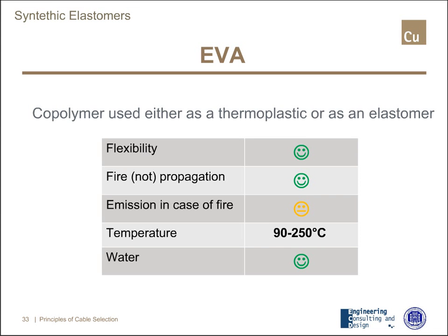EVA — ethylene vinyl acetate. Flexibility is good. Fire propagation: good. Unfortunately, emission in case of fire is not so good; again, we have to consider additives. Temperature is good, 90 to 250°C, and EVA in case of water is still good.